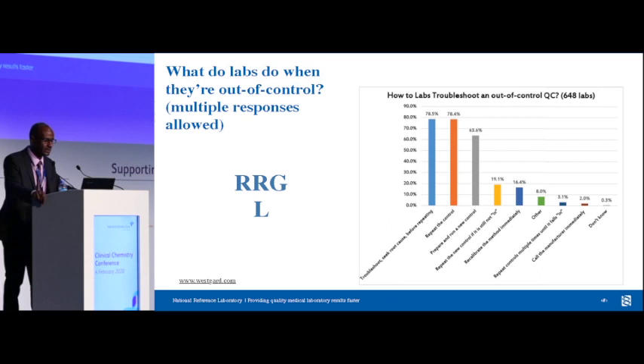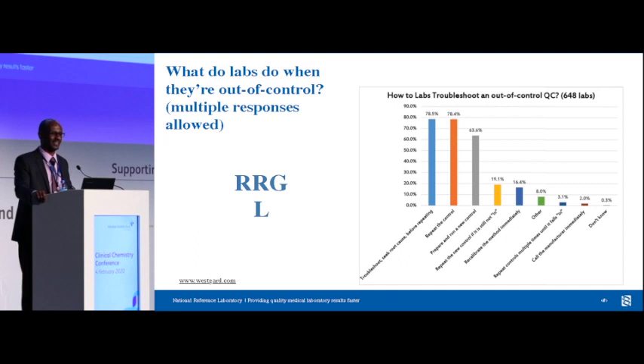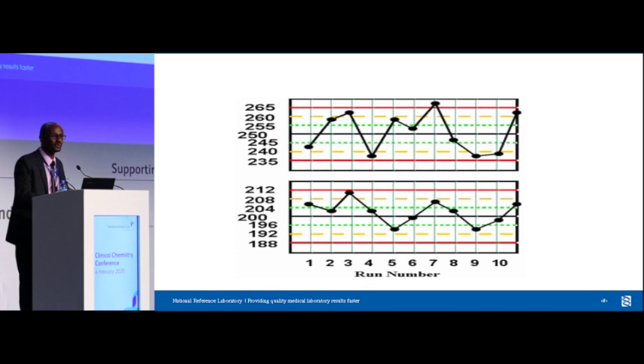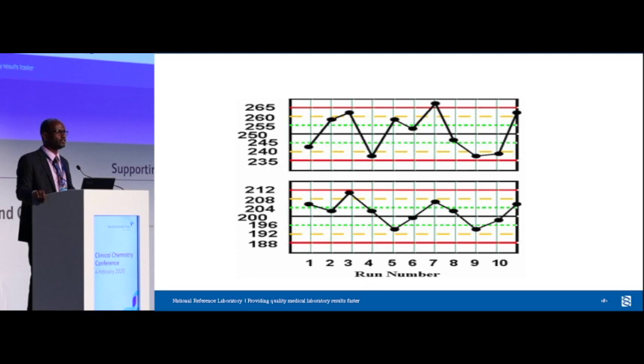What should we do with QC out of range? Up to 78% said repeat the quality control. Repeating QC is not a good practice. Westgard likes to write 'RRGL' — Repeat, Repeat, Get Lucky. You just keep repeating until the QC is in. We should not do that. We need to look at the two QC charts side by side and assess what happened — do we have a systematic failure or a random error?